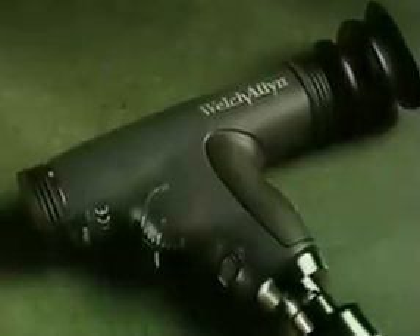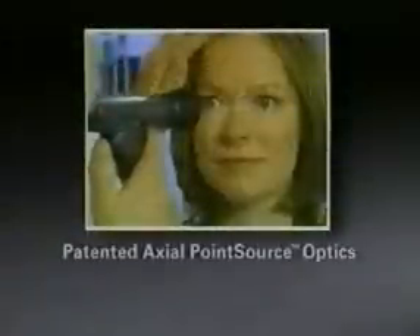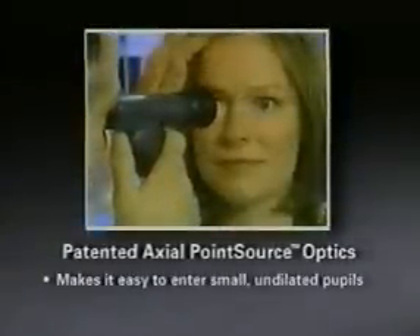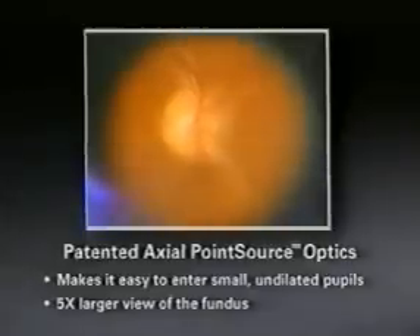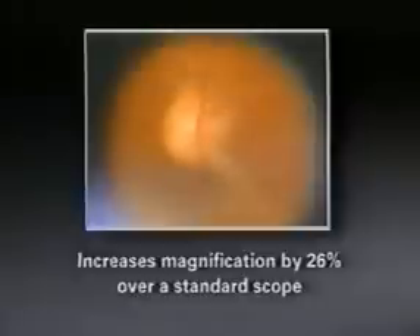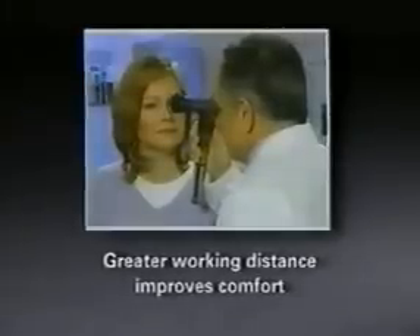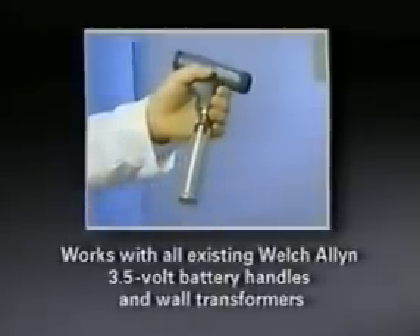The Welch Allyn Panoptic is a revolutionary new concept in ophthalmoscopy with an innovative new optics design. The Panoptic's patented axial point source optics makes it easy to enter small, undilated pupils and provides a view of the fundus that's five times larger than ever before achieved with a standard ophthalmoscope in an undilated eye, with a 25-degree field of view compared to a standard ophthalmoscope's 5-degree field of view. The Panoptic also gives you a 26% increase in magnification and a much greater working distance between practitioner and patient, improving comfort during the exam. Additionally, the Panoptic works with your existing Welch Allyn 3.5-volt battery handles and wall transformers.